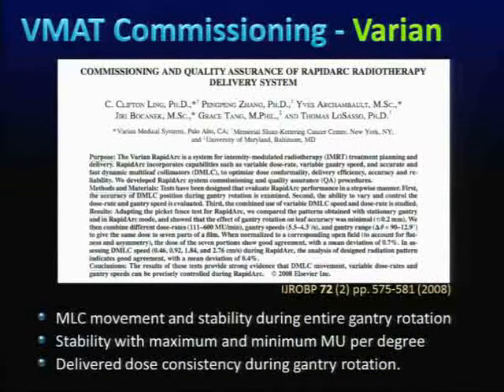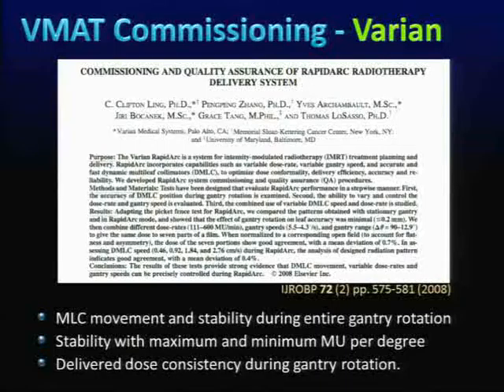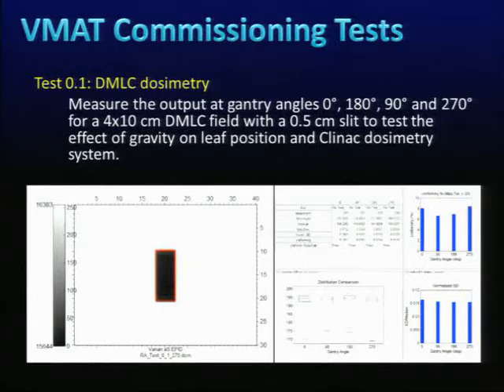For VMAT commissioning on Varian machines, a key reference paper covers MLC movement and stability during gantry rotation, including maximum and minimum MU per degree and delivery dose consistency. Test 0.1 involves DMLC dosimetry at different gantry angles using an ion chamber at the central field or using EPID or film, analyzing each gantry angle to confirm there is no dose difference.